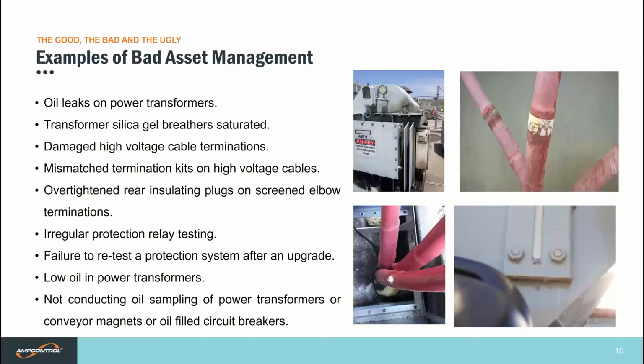With regards to all high voltage terminations, these require an air gap between phases and phases to earth, and also in the case of parallel cores, which are both bolted onto the same phase. Adding an insulation material between the power cores and a frame or support only makes that situation worse. And again, that will be shown later on with one of our case studies. We come across a lot of 600-volt PVC tape wrapped around a power core termination as the phase color ID. All high voltage terminations have leakage on them. To stop or interrupt that leakage by the application of tapes can have long-term failure issues.